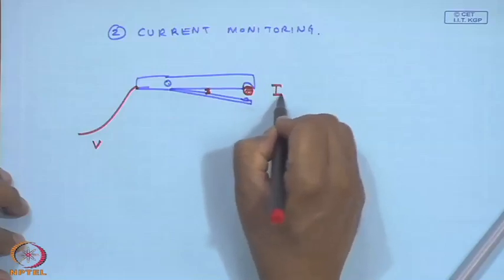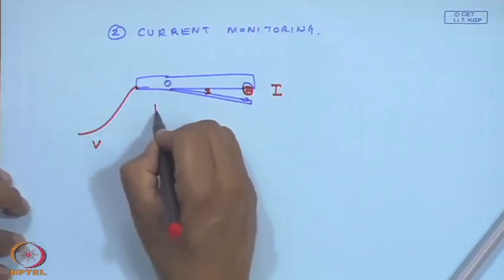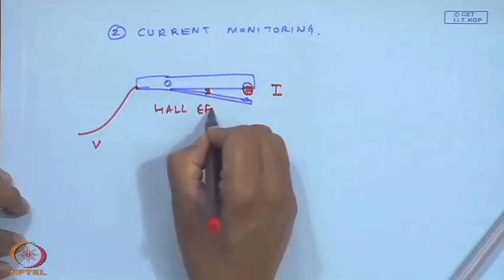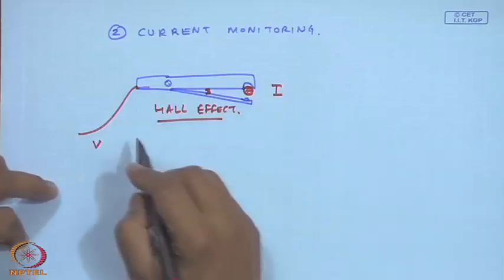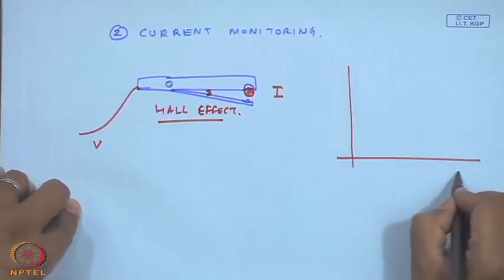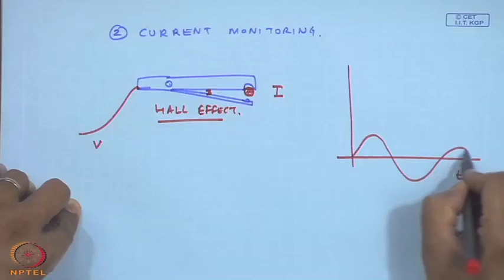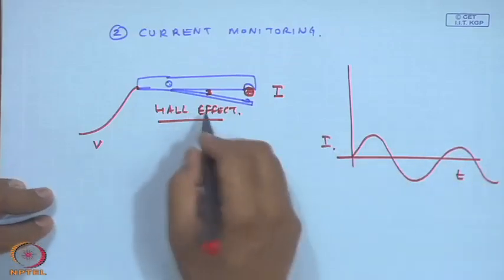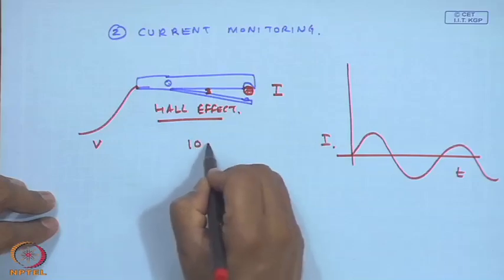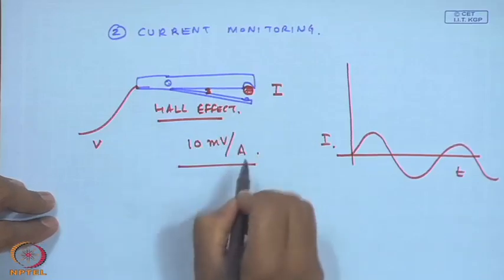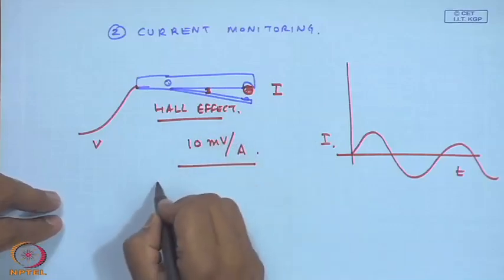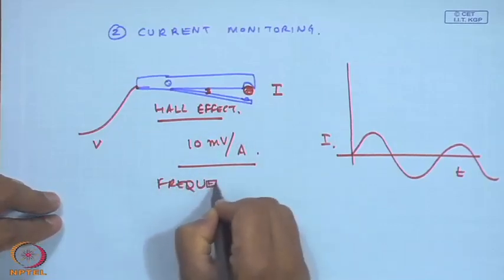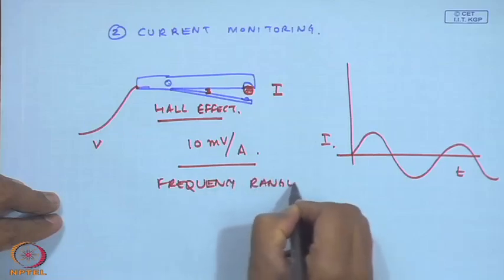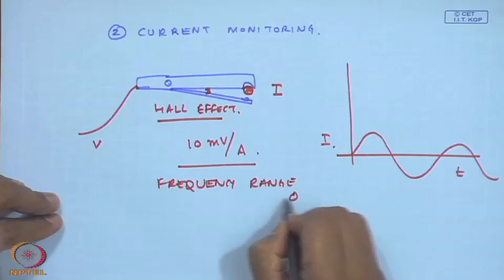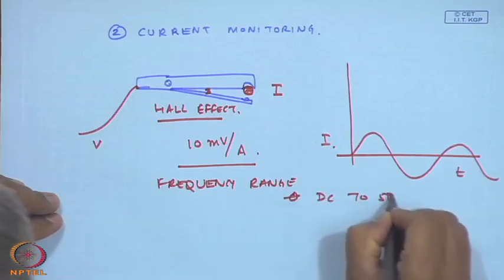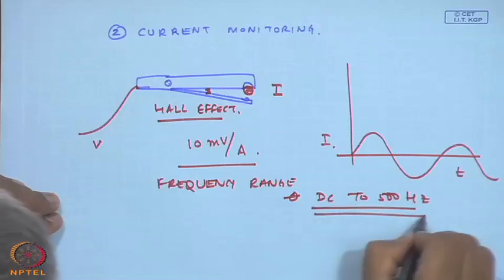So, if I am measuring a current, I will get a voltage here because of the Hall effect. Okay. I will get a voltage which is proportional to the current, and with time I can be measuring the current. Usually Hall effect sensors have a sensitivity of maybe 10 millivolt per ampere, etc. The reason we are using Hall effect sensors is because they have a high frequency range, all the way from 0 or DC to about 500 hertz, that I can measure with such Hall effect sensors.